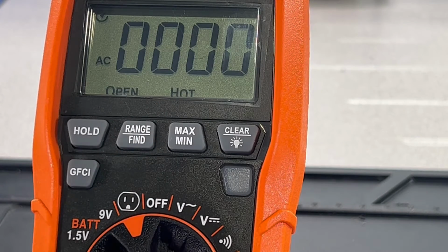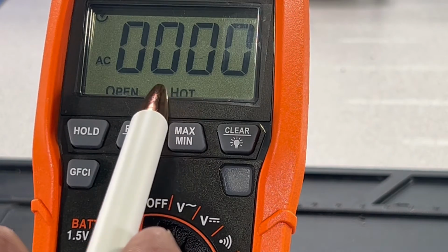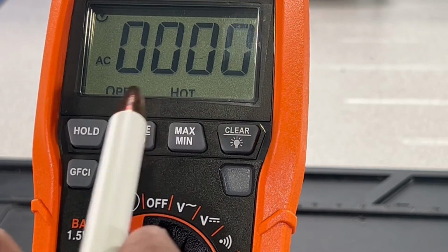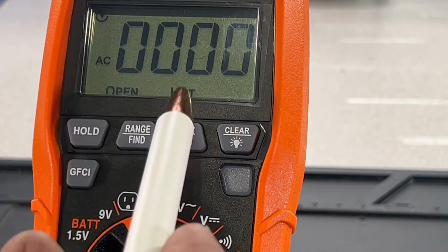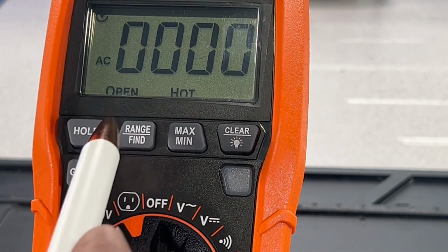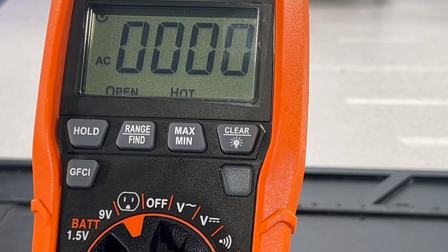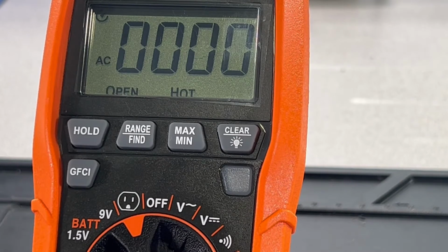Also, if the wires were reversed, it'll read out what all it does. It will probably show wires reversed, open, neutral, shared neutral, or false ground, things like that. I really didn't know it did all of that until I went back and started looking at the manual, and I experienced some of those things. I created some of those faults, and it does do that.